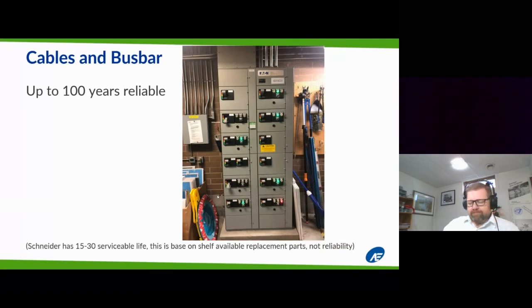Cables and bus bars can last up to about 100 years reliably. Now, where do we get this data? There's not a lot of cables from 100 years ago using the same technology today. This is based on IEEE data, collected from industrial sites, so they've got some pretty good approximations. They don't know for sure, but I think if you install a wire in the 1980s, you'll probably get about 100 years out of it. Bus bar, as long as it's not corroded, should last about 100 years.